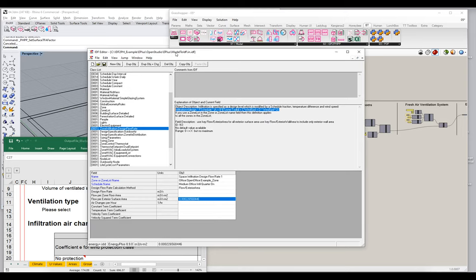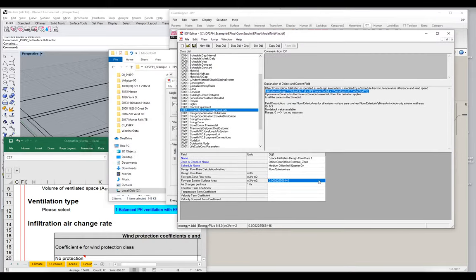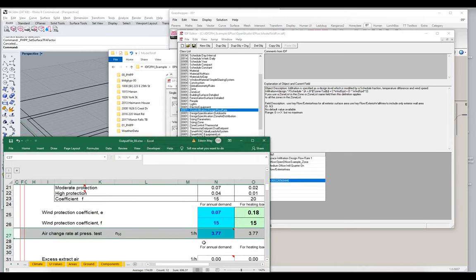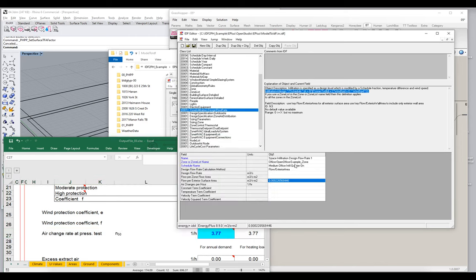We can do the math — it's not too complicated. If you take this airflow number, this schedule, and some of the other inputs, what you end up with for this building is an air change rate of 3.77. If you work backwards and take all the schedules into account, you get a constant or average flow rate of 3.77 for this building. This is all based on some sort of default library value for an office type project.